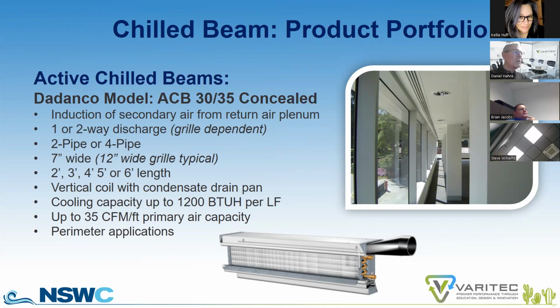What they do in that project is that when the outdoor dew point or humidity is at a certain point, they'll actually change the chiller from supplying 55-degree chill water down to 44-degree chill water to the chill beams. So they become condensing devices, and they can actually maintain space humidity. I was hesitant to embrace this concept at first, but then it dawned on me, well, what's the difference between a condensing active chill beam and a fan coil unit condensing at the coil of a fan coil unit? And providing you have drain pans and condensate pumps where necessary, you can certainly do that.